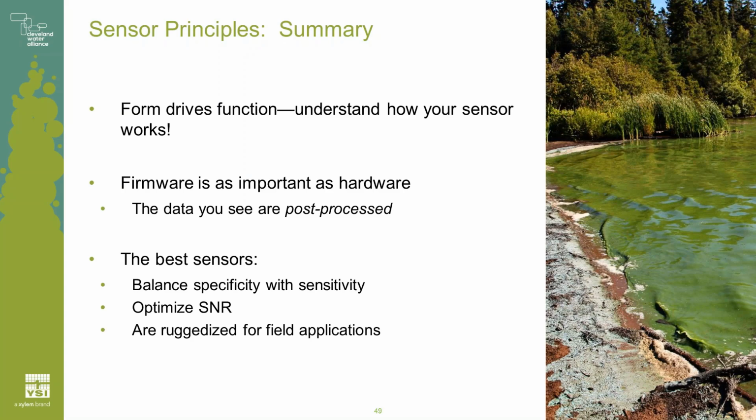Martin asked me to comment more on interference. So for example, he said that he's getting higher chlorophyll and phycocyanin readings near the bottom of his reservoir when turbidity is higher. This is something that we have heard before, and it's definitely something that older sensors and what we call single channel sensors are much more prone to than the EXO sensors.